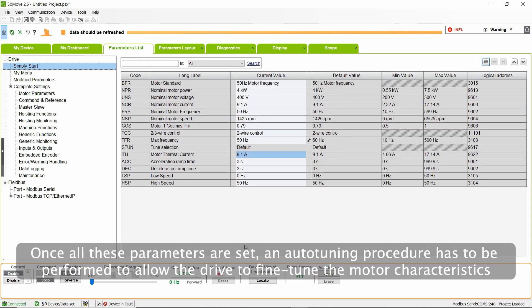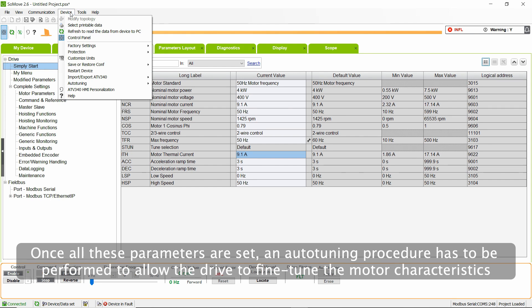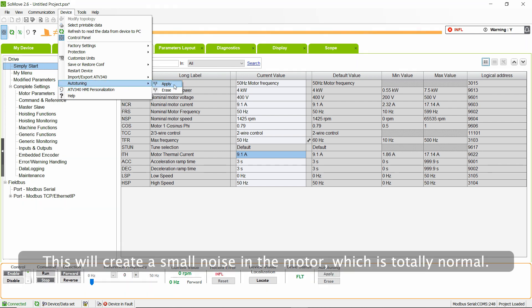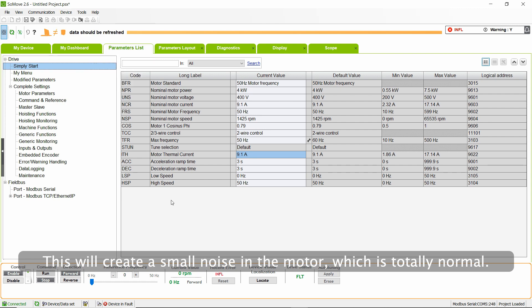Once all these parameters are set, an auto-tuning procedure has to be performed to allow the drive to fine-tune the motor characteristics. This will create a small noise in the motor, which is totally normal.